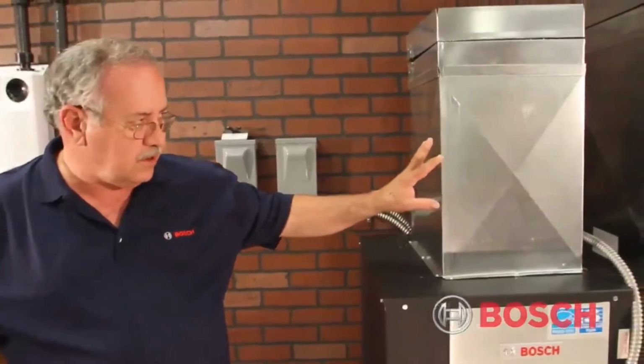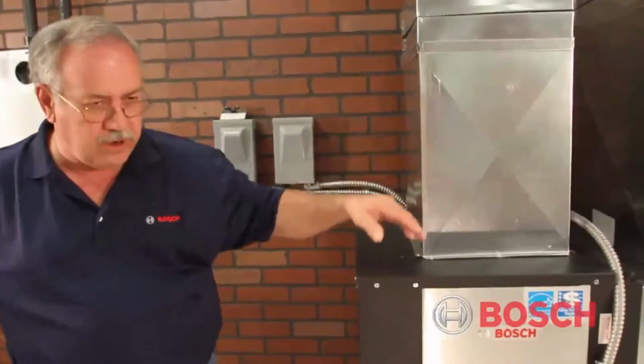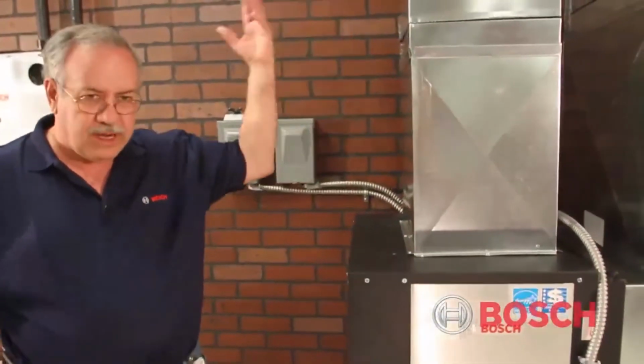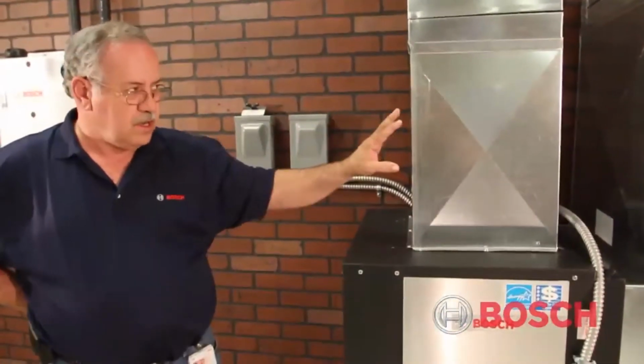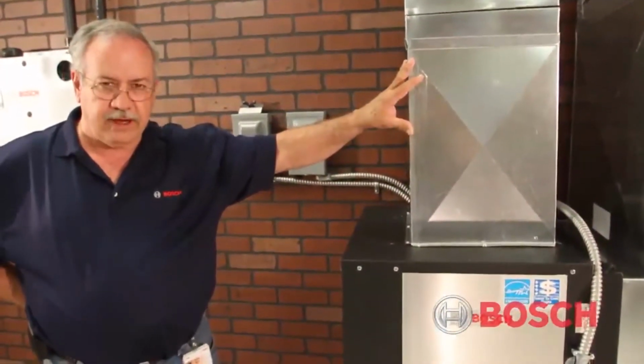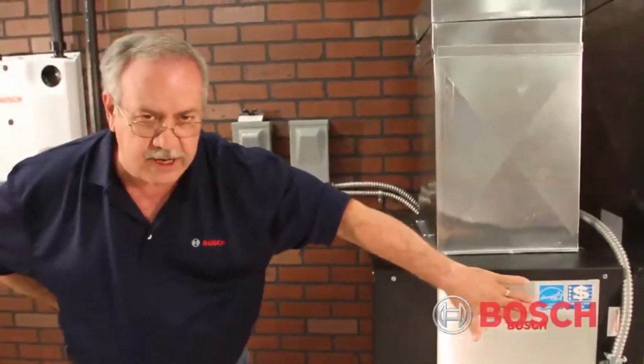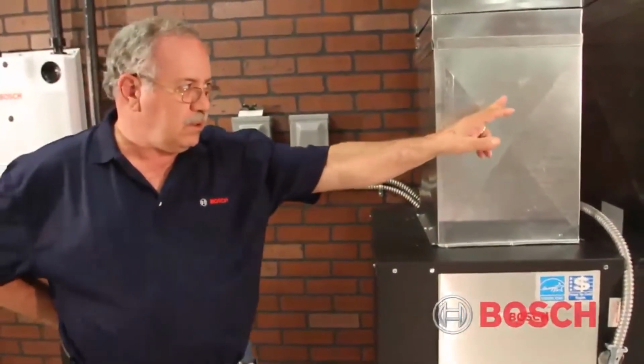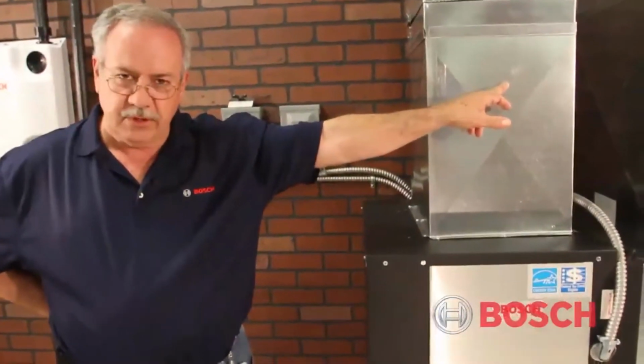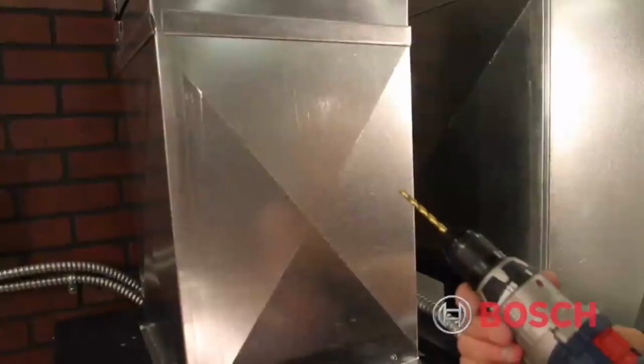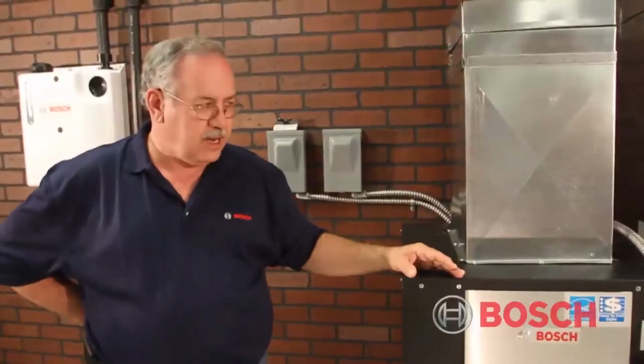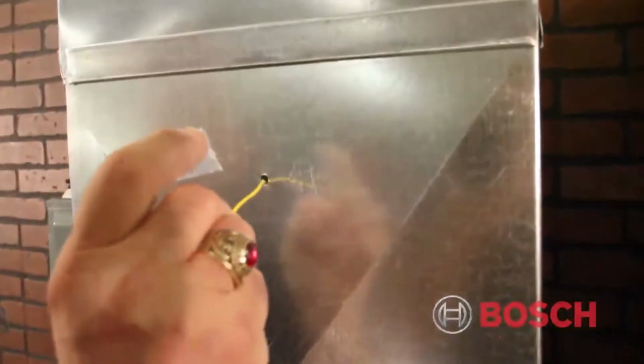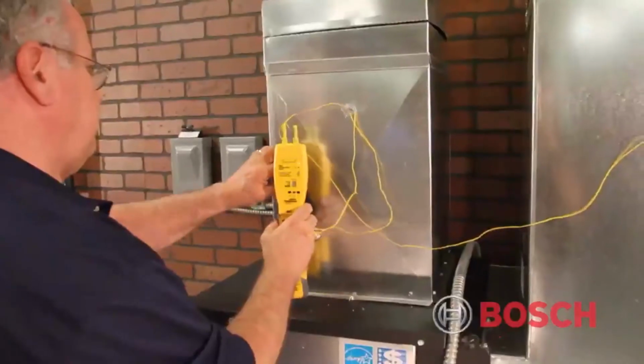All right, in the field, to check CFM by temperature rise across the heater, what we'll have to do is go to the existing unit. Here we show the supply air plenum and the return air plenum. Typically this will be connected to ductwork in the structure. We try to get away from the radiant heat effect of the heater, which is right here inside the top of the unit. But today we'll drill 2 holes, one here and one in the return. Typically we would want to get farther away from the unit itself to do this, but for illustration we'll show this. We would connect to this a temperature analyzer that would show supply and return air temperatures while it's running.